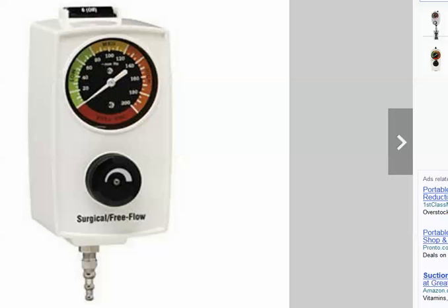So first of all, the vacuum regulator is going to be set on the wall, and usually is a quick connect device, much like your oxygen hoses. And there's an adjustment here. Okay, this actually is the adjustment part. And then up here you may have some sort of intermittent type setting, whether it's continuous or off or intermittent. That's what we look for up here. And then, of course, this is the amount of vacuum pressure that's applied to the suction catheter itself.